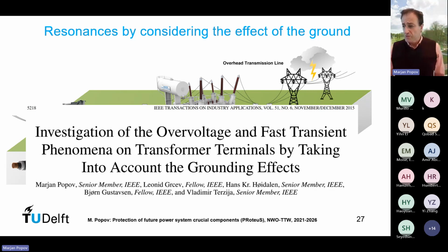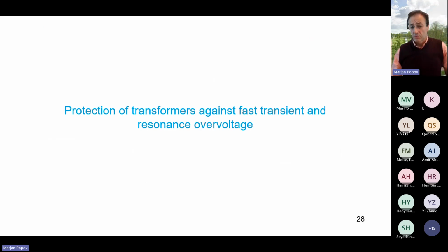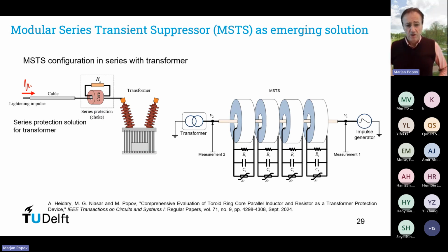This kind of work was conducted nearly 10 years ago. I will refer the readers to this paper, Investigation of the Overvoltage and Fast Transient Phenomena on Transformer Terminals by Taking into Account the Grounding Effects. It was published in IEEE Transactions on Industry Applications, where we accurately modeled the overhead lines, the grounding system, the transformer, and the surge arrester. The next step is to develop devices to protect transformers against fast transients and resonance overvoltages. This is part of an ongoing project.